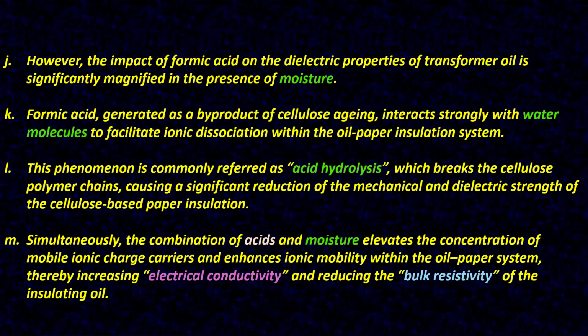This phenomenon is commonly referred to as acid hydrolysis, which breaks the cellulose polymer chains, causing a significant reduction of the mechanical and dielectric strength of the cellulose-based paper insulation.